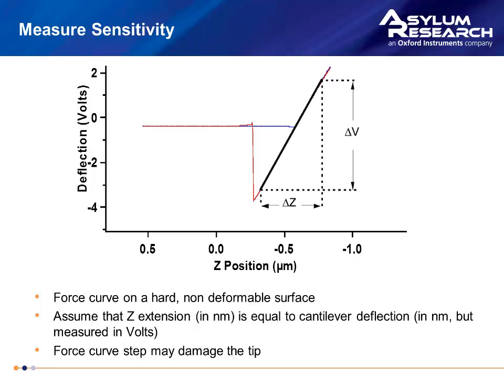The most common way to calibrate the sensitivity of a cantilever is to perform a force curve on a hard surface. With a hard surface, we can assume that the sample doesn't deform as we press against it. Once we have that data, we can assume that the change in voltage measured by the photodetector is equal to the distance in nanometers that the Z piezo is pushed with, and that's how we get our sensitivity.